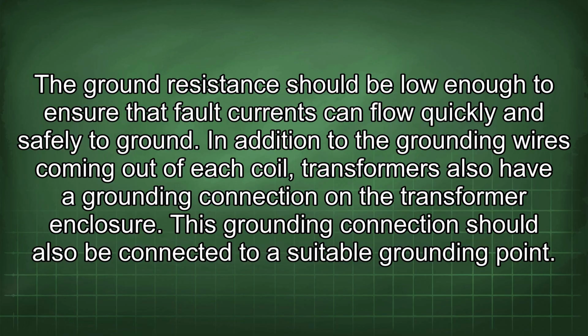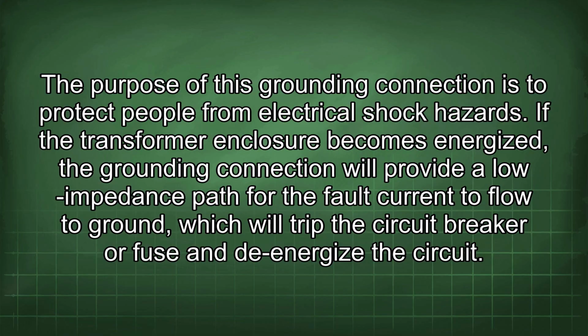In addition to the grounding wires coming out of each coil, transformers also have a grounding connection on the transformer enclosure. This grounding connection should also be connected to a suitable grounding point. The purpose of this grounding connection is to protect people from electrical shock hazards. If the transformer enclosure becomes energized, the grounding connection will provide a low impedance path for the fault current to flow to ground, which will trip the circuit breaker or fuse and de-energize the circuit.